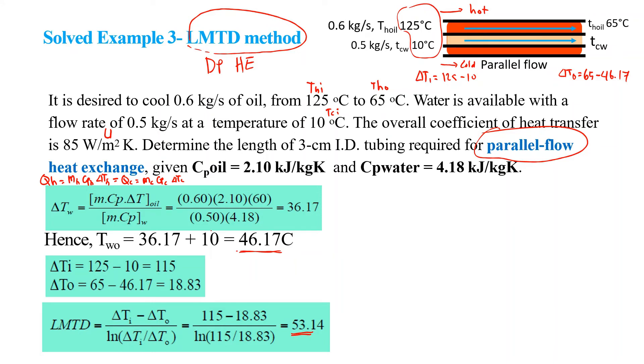Next, since the problem requires the area or the length of the pipe, we need to find out first the total area required. We can use the general equation Q = U·A·LMTD. We have LMTD and U given, so we need to find Q.